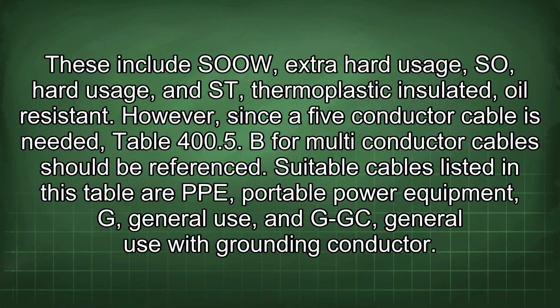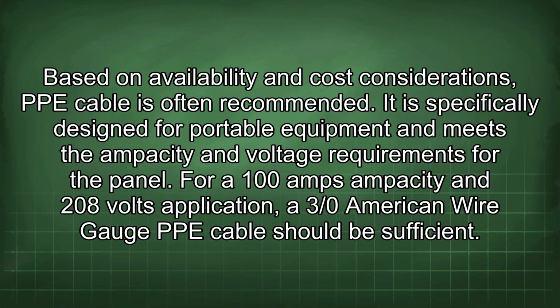These include SOOW, extra hard usage, SO, hard usage, and ST, thermoplastic insulated, oil-resistant. However, since a 5-conductor cable is needed, Table 400.5(B) for multi-conductor cables should be referenced. Suitable cables listed in this table are PPE, portable power equipment, G, general use, and G-GC, general use with grounding conductor. Based on availability and cost considerations, PPE cable is often recommended.